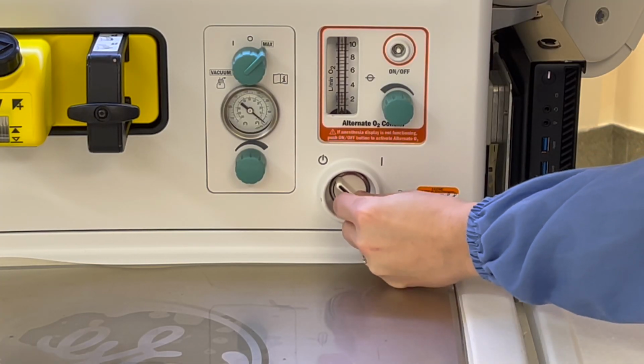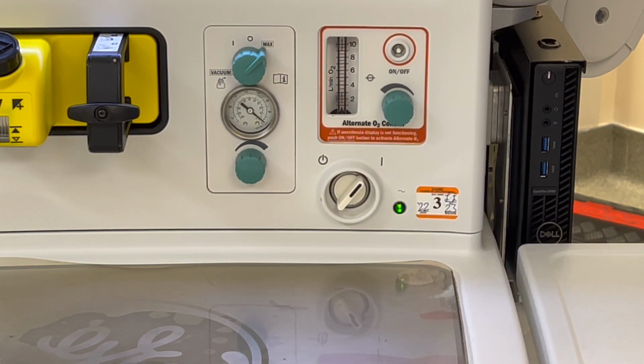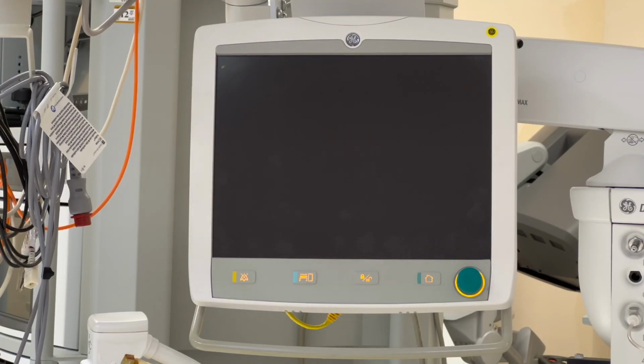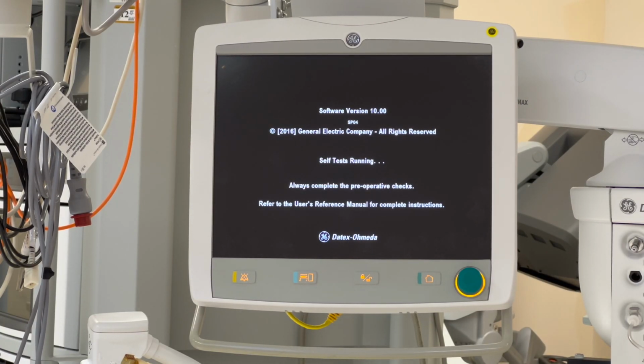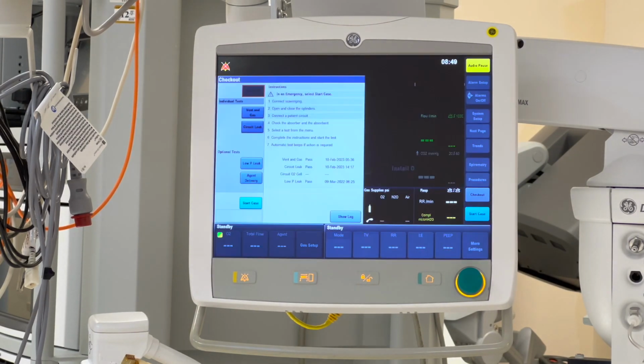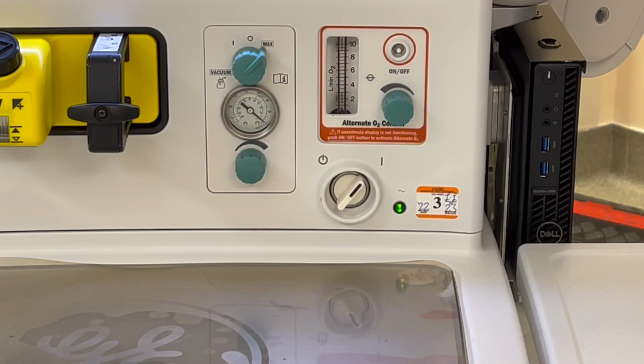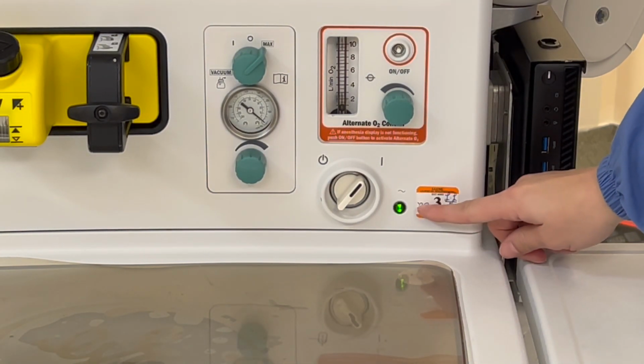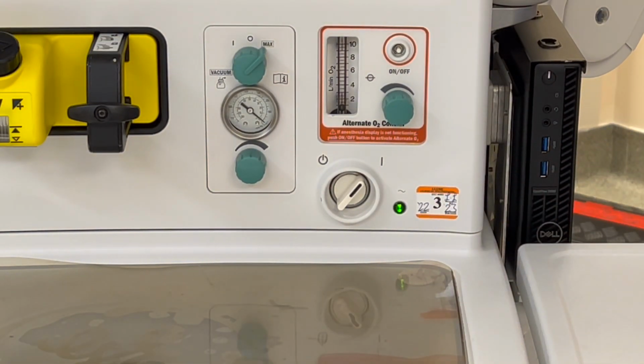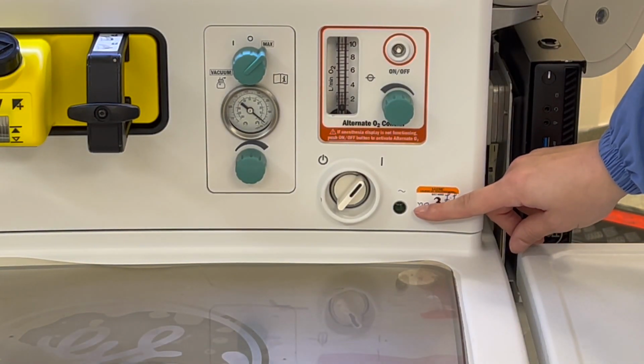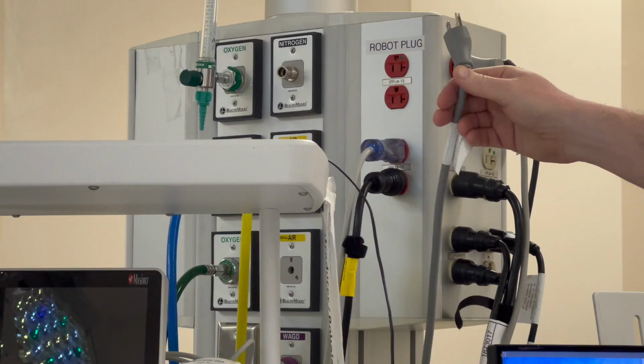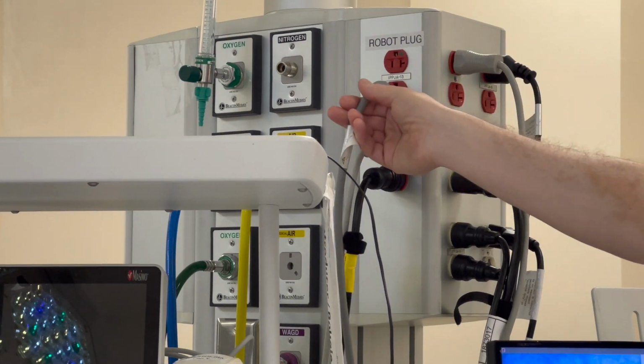Turn on the anesthesia machine by turning this switch to the right. The machine will do a series of self-tests. If the machine is already on in the morning, turn it off and back on again to ensure these tests are completed. Notice the green LED indicator that signals you are currently connected to AC power. Should you get disconnected from the wall or if there is a power failure, then this light will turn off. If the light is off, this indicates that you are on battery power.